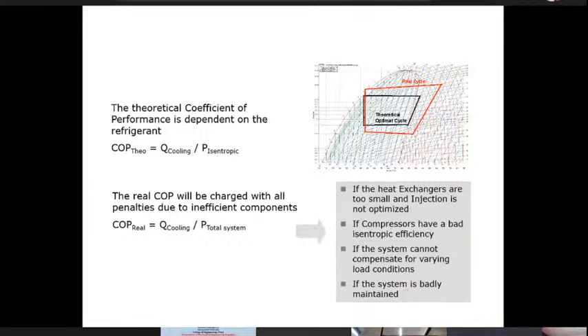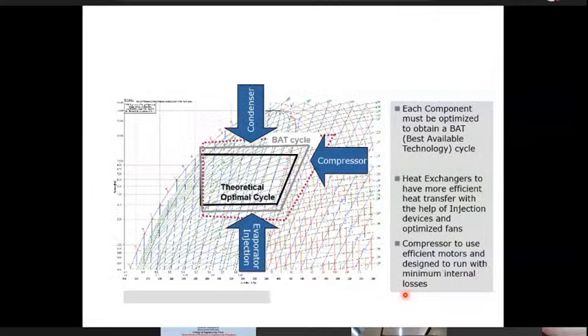So when we are looking at optimizing systems, we will look at optimizing each and every component. Looking at the dotted line representing the technology without innovation, and the cycle represented in black representing the theoretical optimal cycle, we are actually trying to drive this whole technology process from the dotted red line to the gray line. Somewhere between these two, we can reach a point which will be a solution which has a lower energy footprint, and to that extent it will be more sustainable. So one is we improve the circuiting, we reduce the temperature difference in the evaporator, and that would be one way of getting this line shift from here to here.